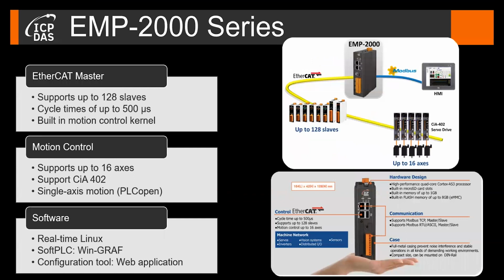The EMP2000 series is a compact PLC with a real-time EtherCAT master and PLCopen-defined single-axis motion control functions. The EMP2000 is ICP-DAS's entry-level motion controller, which controls up to 128 slaves and 16 axes. The integrated motion functions are limited mainly to single-axis control.